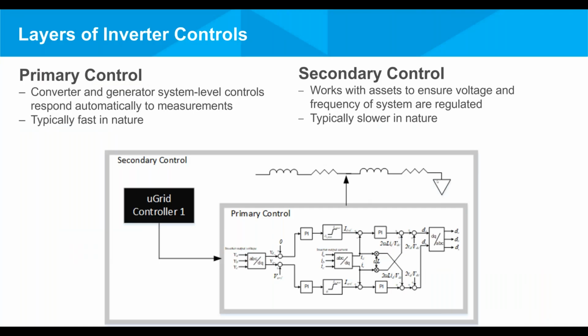Now, moving from the capacity and functionality, the next thing that one has to understand is the control. How should the microgrid be controlled, and in coordination with the different appliances in the smart homes? There are different layers of controls for the microgrid. For the primary control, we're looking at the converter and generator system level controls and how they respond automatically to measurements. This is typically fast in nature. And the next one is the secondary control, where it works with the assets. The key thing here is to regulate the voltage and frequency, and this is typically slower in nature.